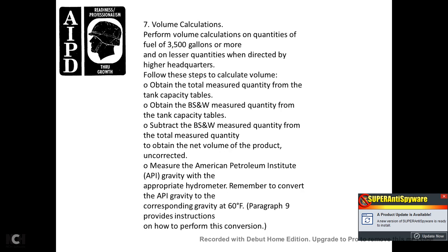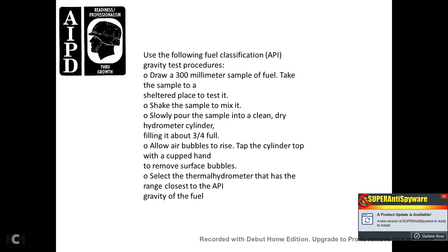Volume calculations. Perform volume calculations for quantities of fuel of 3,500 gallons or more, and for lesser quantities when directed by higher headquarters. Follow these steps to calculate volume: obtain the total measured quantity from the tank capacity tables; obtain the bottom sediment and water measured quantity from the tank capacity tables; subtract the bottom sediment and water from the total measured quantity to obtain the net volume of the product, uncorrected. Measure the API gravity using a hydrometer; convert the observed API gravity to the corresponding gravity at 60 degrees Fahrenheit as instructed in paragraph 9.